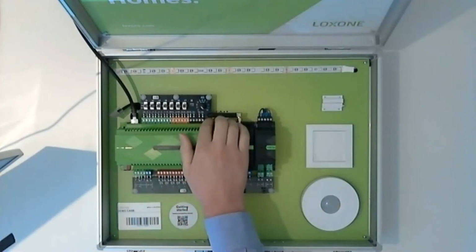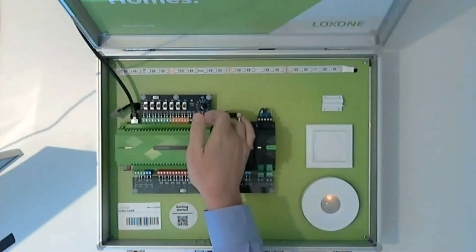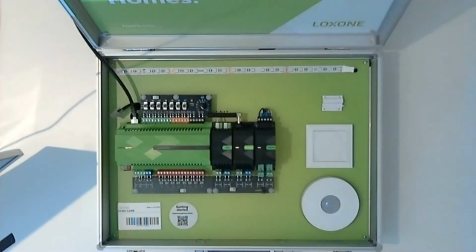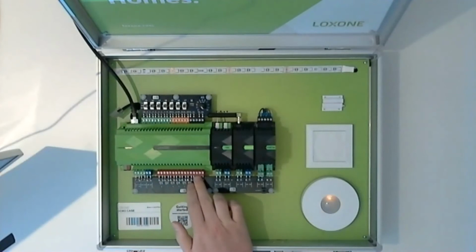Then we move on to the outputs. These are analog outputs. So again, if we need to control something that is variable. My best kind of example of an analog output would be sometimes when we buy LED drivers, they are 0 to 10 or 1 to 10 volt dimming drivers. So you provide a 1 to 10 or 0 to 10 volt signal to say how bright you want the light. And that is an analog output. And then at the bottom, the red ones are digital outputs.